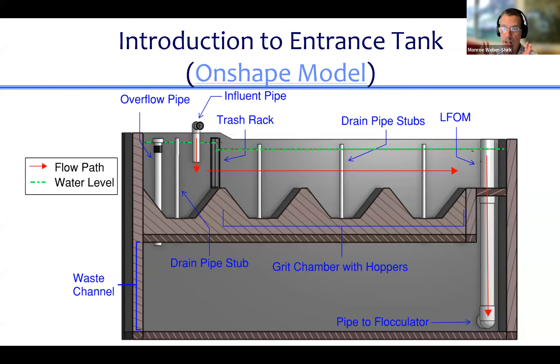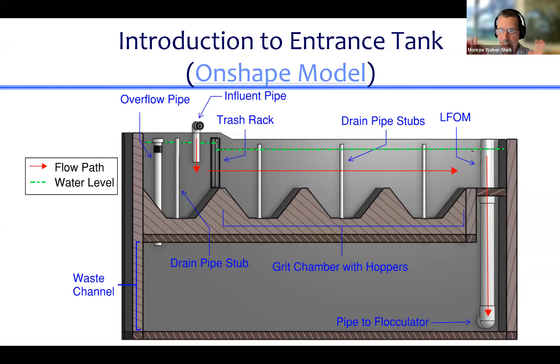The other thing in the water that would be a nuisance in the rest of the plant is grit - think sand and slightly smaller particles that are heavy enough to settle out quickly. If we don't capture them here, they'll settle in the next process, the flocculator. It just accumulates in the bottom and operators have to pull the baffles out to clean it, so we prefer to take the grit out in the entrance tank.